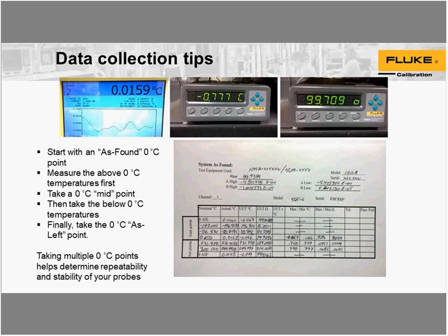Okay. We always start with a 0 degree reading. And I'll explain this as we go on. But the 0 as found. Then we take the above 0 degree temperatures first, take another 0 degree at midpoint, and then we take the below 0 temperatures, and finally we take another 0 as left point. The reason we take multiple 0 degree points is because we can watch the probe changing through the different temperatures. If it is shifting, if it is not repeating the resistance very well, we may have a problem with the probe. And that's one thing that we'd like to use as a diagnostic tool as well.